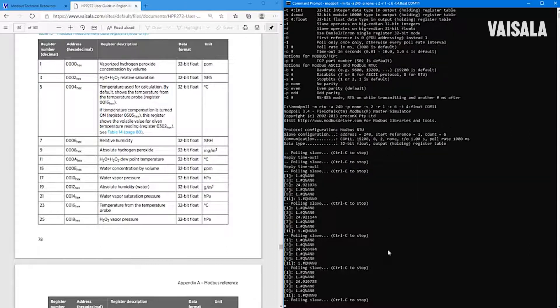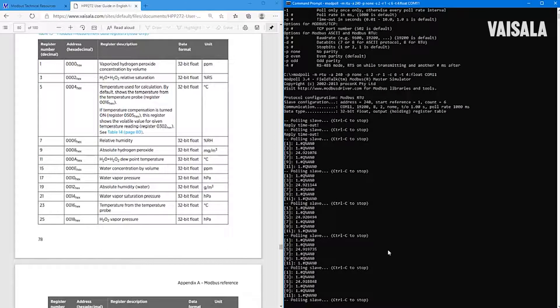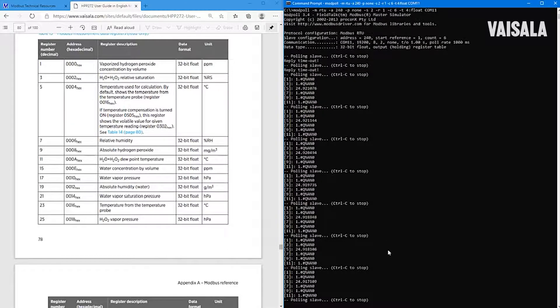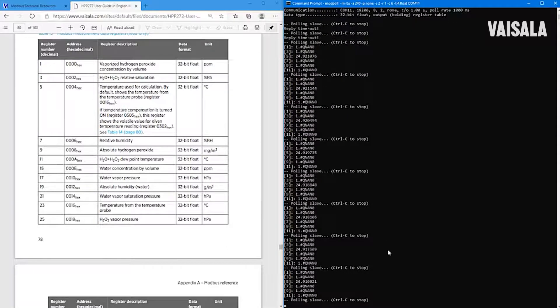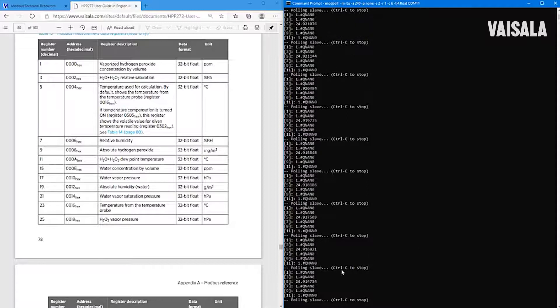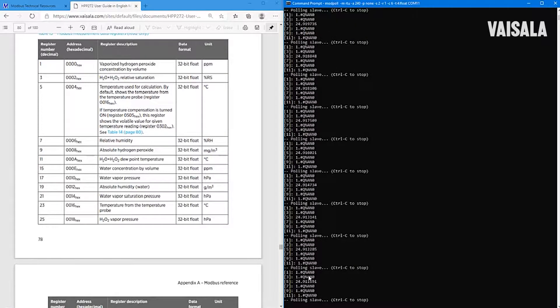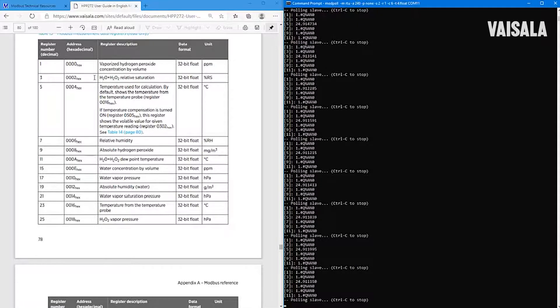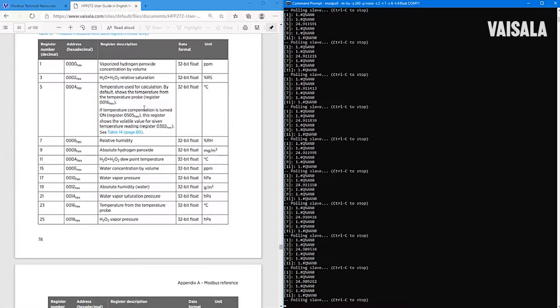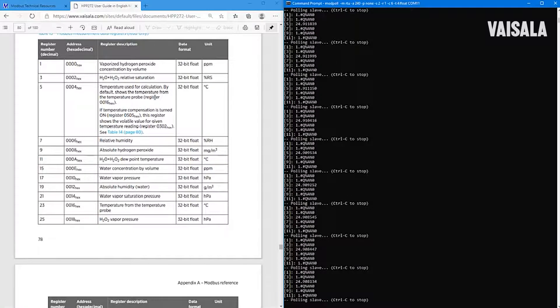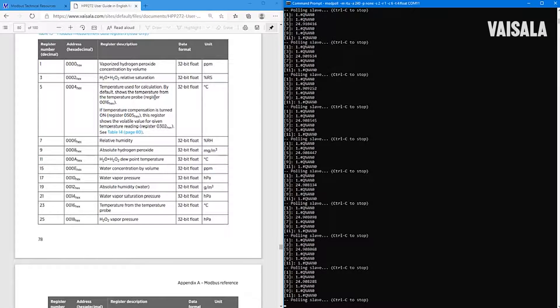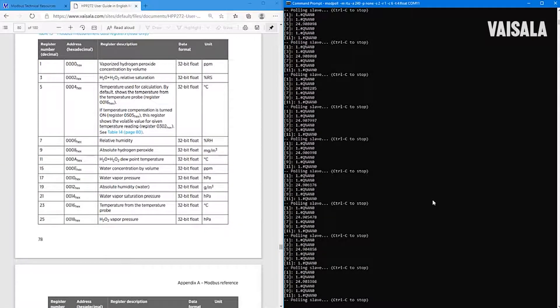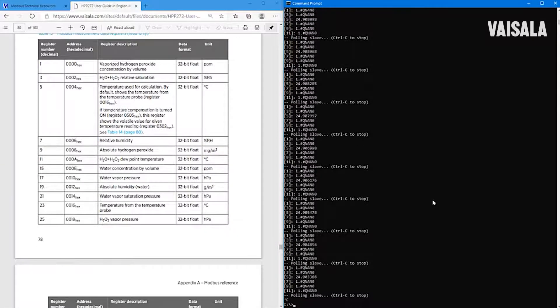And here we have values. And if we diagnose what kind of values we get there, we can see that there are not a number for the first register and second. And the third register actually gives us a value, and this is the temperature. And the reason why we cannot get any values is that this probe is currently in a purge mode. And how do we know that?